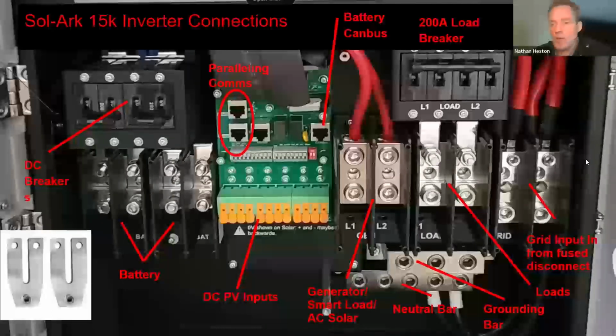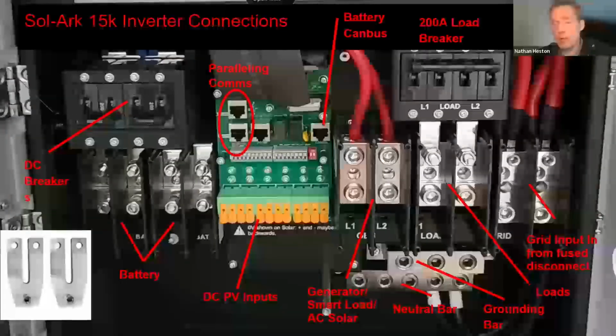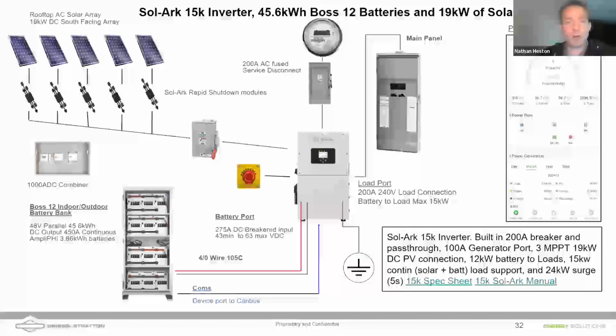And on the right side of the screen, of course, that's your grid input, your L1 and your L2 for split phase. These inverters, of course, can do 3-phase as well. So if you've got a 3-phase Y configuration, you can do 208. If you've got a 3-phase delta, we need to run through a transformer, but we can do that as well. So I'll talk about that a little bit later if there are questions.